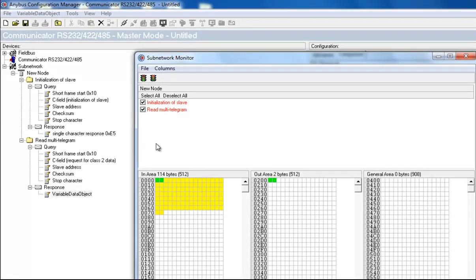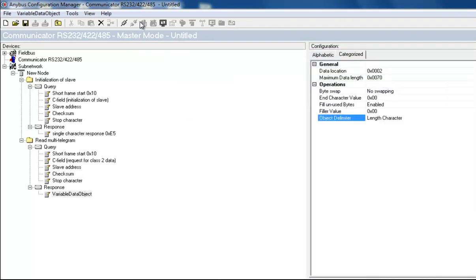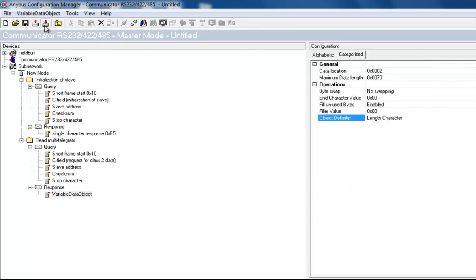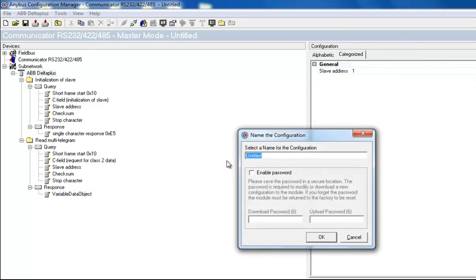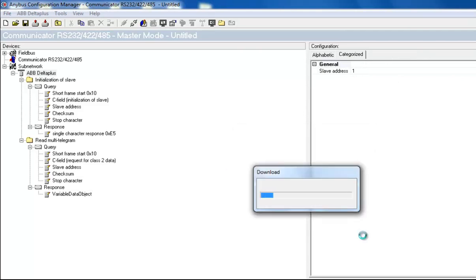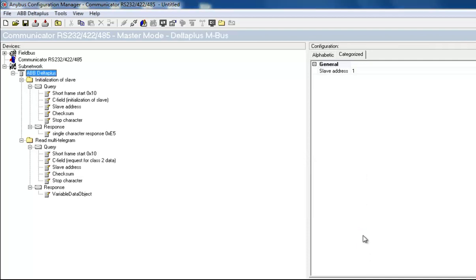I go back to the subnetwork monitor, where I can see my trigger bytes in green and my response bytes in yellow. I click connect, and then download the configuration to the Anybus communicator. I have now enabled communication between the MBUS energy meter and the industrial network, in this case Profibus.